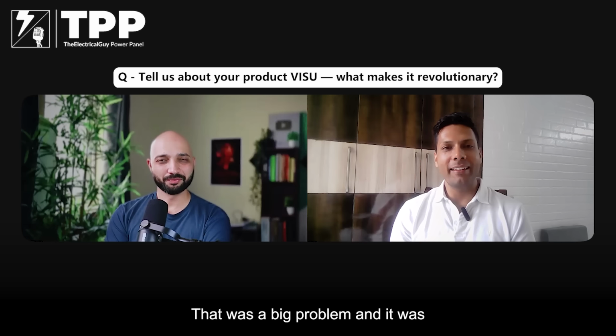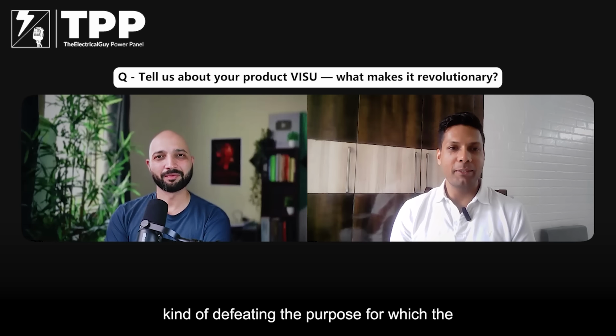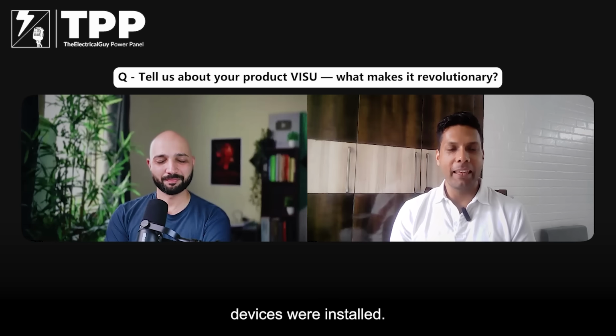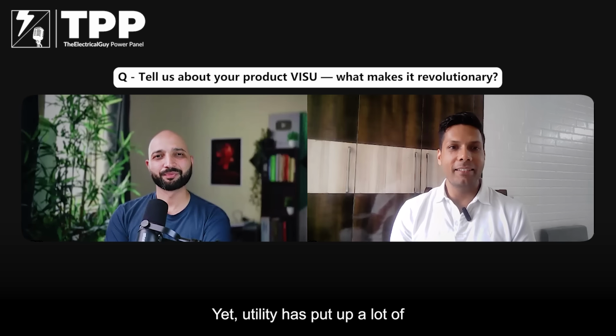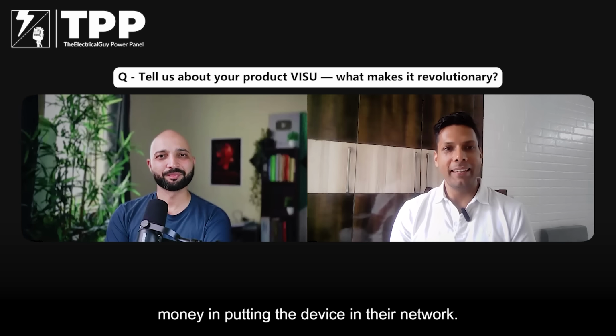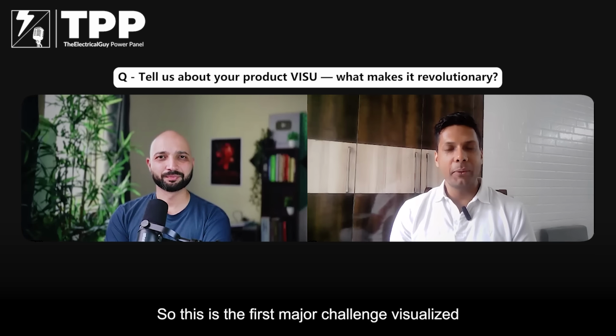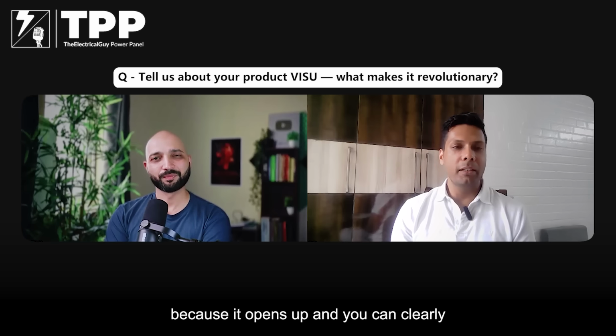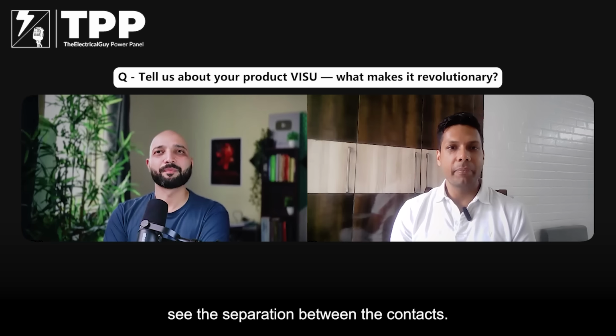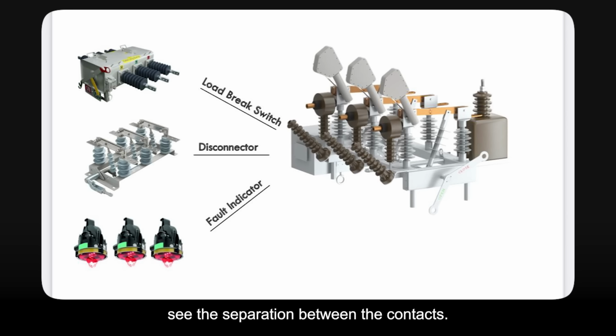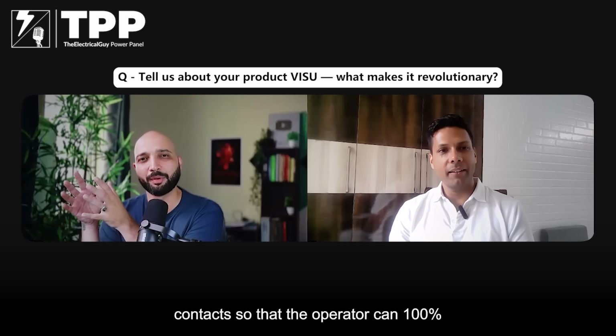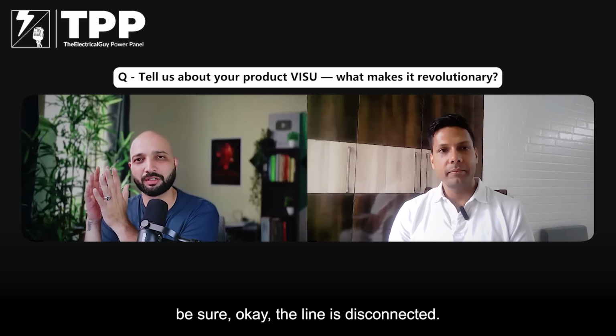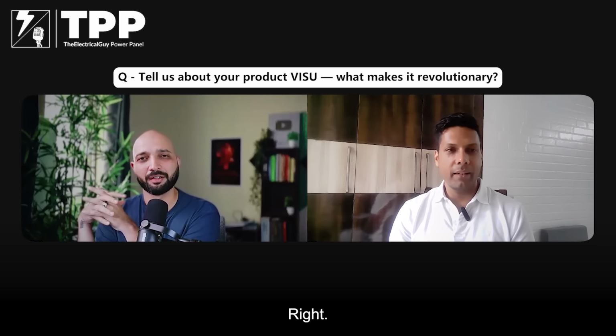That was a big problem, and it was kind of defeating the purpose for which the devices were installed. Yet the utility has put up a lot of money in putting the device in their network. So this is the first major challenge which you addressed, because it opens up and you can clearly see the separation between the contacts. So there is clear visible disconnection of the contact so that the operator can be 100% sure that the line is disconnected.